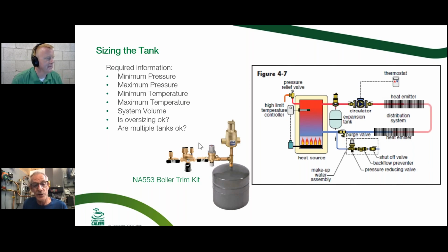So how do I size a tank? There is a slightly different formula for compression tanks as opposed to a diaphragm type of tank. Both formulas are in there. You want to know what the fluid is. Is it water? Is it glycol, and what percentage? The minimum pressure that you're going to fill the system, your static fill pressure, and the maximum pressure that you can run at. Usually we figure, I think it's coming up on a slide, 27 PSI on a system that has a 30-pound release valve. And then the temperature differential from when you fill it, let's say 55-degree water coming in, up to 200 degrees. The volume is the trickiest number to get when you go into these sizers.